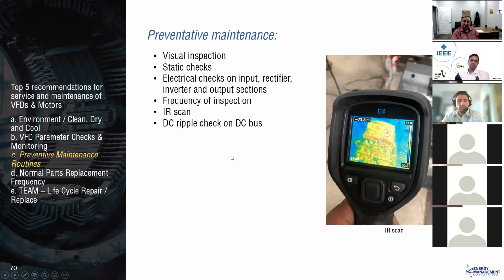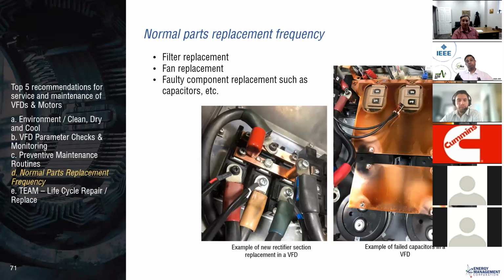One interesting thing we're doing for a large oil company now that's really made a big difference. It might go to this last area about the life cycle repair replace analysis, what we call our total electrical asset management program. We're doing DC ripple checks on the DC bus of all the drives. We're finding some drives that could be 10 years old and have millivolts of ripple, and some that are 1 year old that are actually approaching 10 volts. And we're using that as a means of predicting, because we want to avoid this failure.